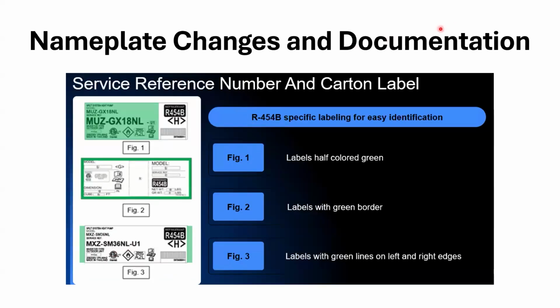And then, nameplate changes and documentation. This stuff here is just basic information, but important because, like I was saying before, what I'm seeing on the support line is I've already had, I think, 3 cases I know of mixing equipment, between the 454 and the 410 equipment. So again, knowing the labeling and the coloring of these labels, so everybody is on board and knows this. When I went to the Gensco customer and picked the outdoor unit, when you pick a smart multi outdoor unit, it flags you for the branch box. So the right equipment is picked in the order. Now, the process when it's pulled in the warehouse, then delivered to your team, and then where it goes from there with your team.